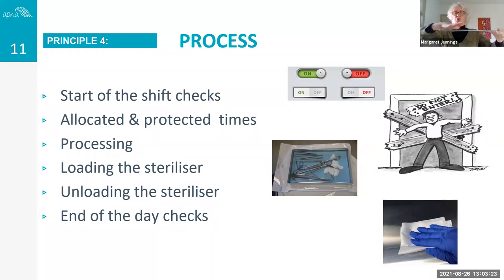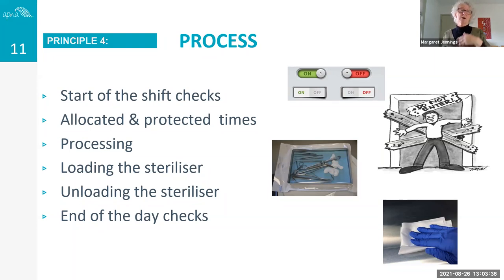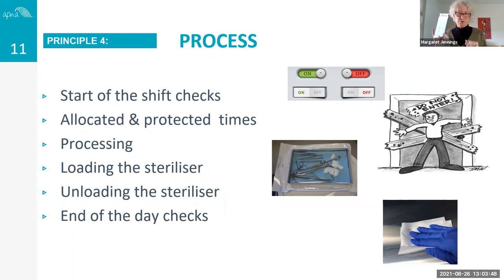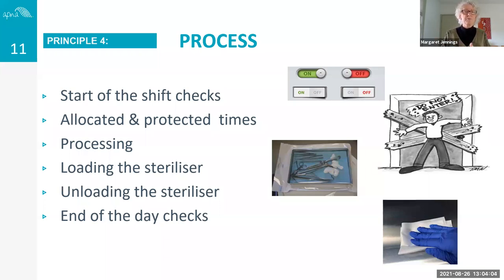Put the whole tray onto a cake rack so air can circulate underneath. Cooling might take 10 to 15 minutes — the pack must be dry when taken out of the sterilizer. Use that time to check whether the cycle worked. With very clean dry hands you can then pick up the pouch. Never touch a warm pouch — bugs from your hands go straight through. Someone needs to be there for 15 minutes after the cycle finishes to open, remove, cool, record results, and put items away. Never leave anything out.